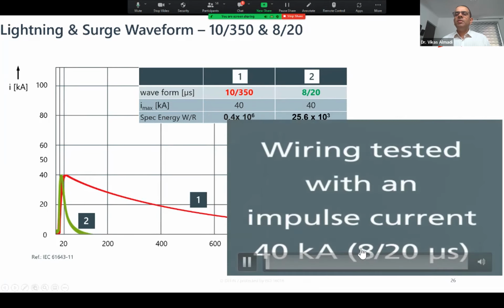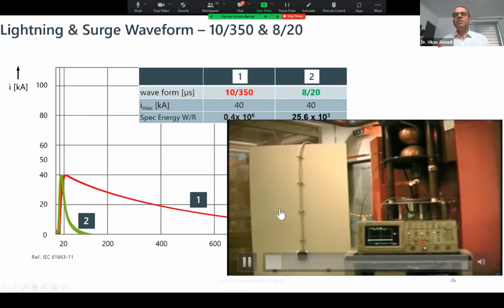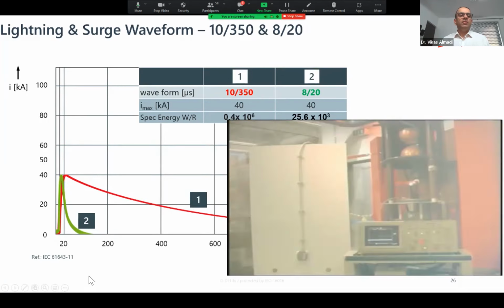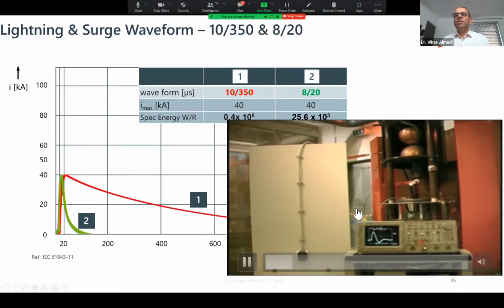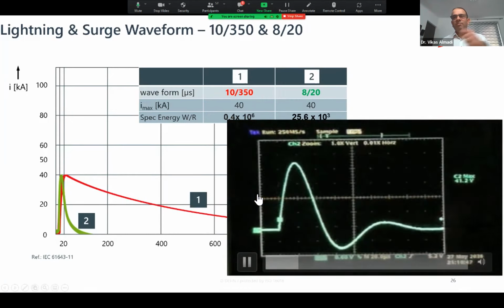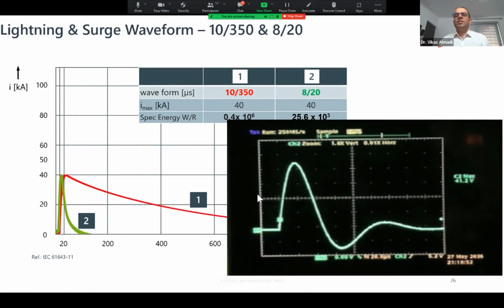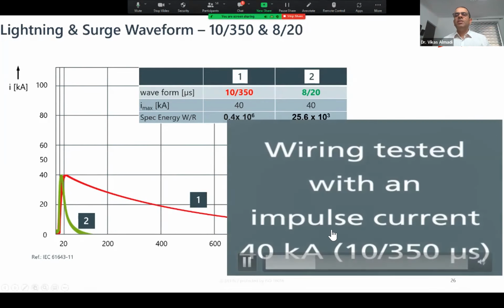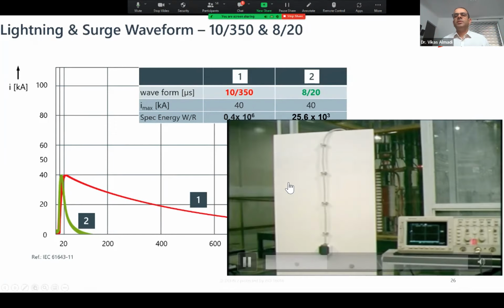This is 8 by 20, 40 kiloampere. So we are putting it to a wire. Actually, this is the wire here, you see. And there is some movement in the wire because current brings some force, but no damage actually. Now you see 10 by 350, same 40 kiloampere with 10 by 350. What happens? Same wire.